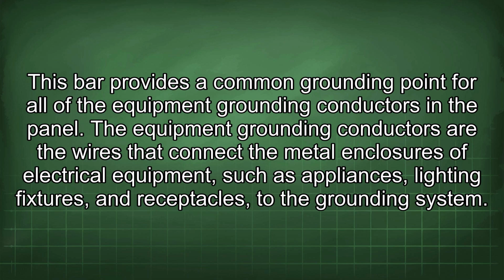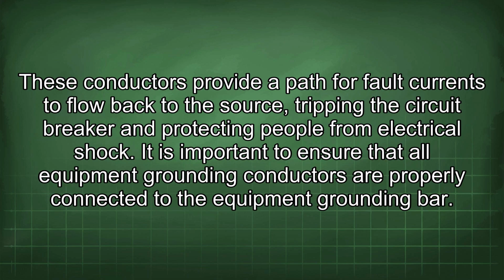The equipment grounding conductors are the wires that connect the metal enclosures of electrical equipment, such as appliances, lighting fixtures, and receptacles, to the grounding system. These conductors provide a path for fault currents to flow back to the source, tripping the circuit breaker and protecting people from electrical shock.